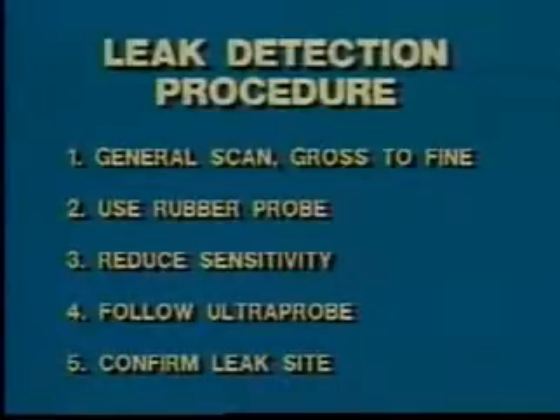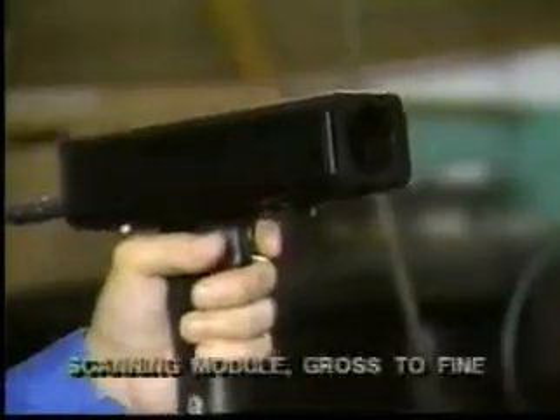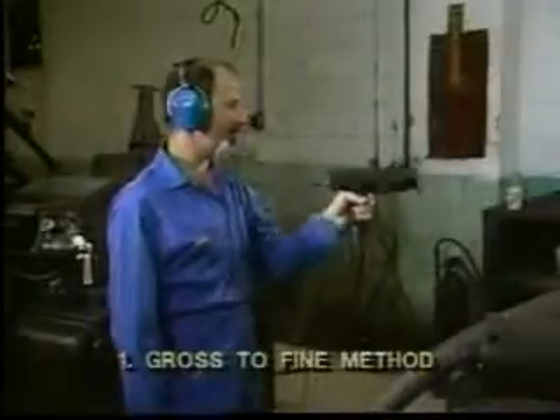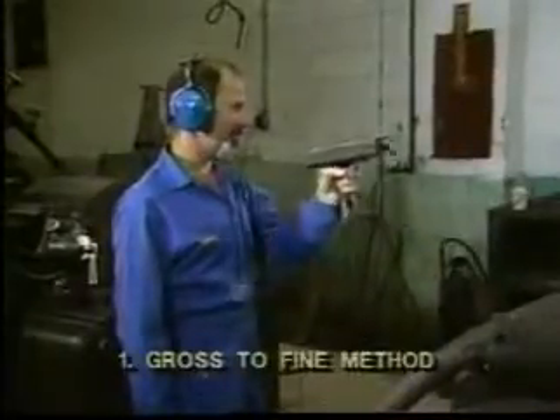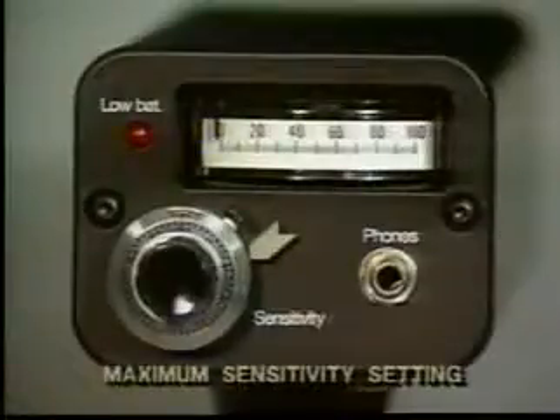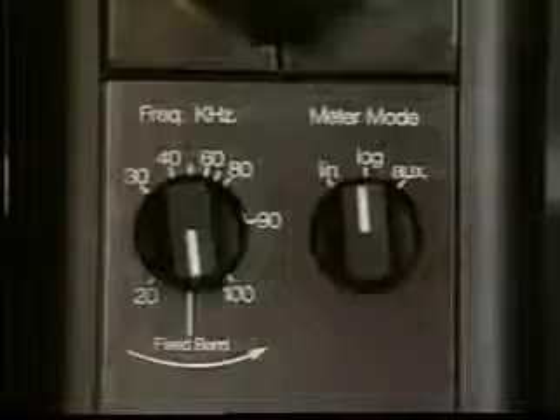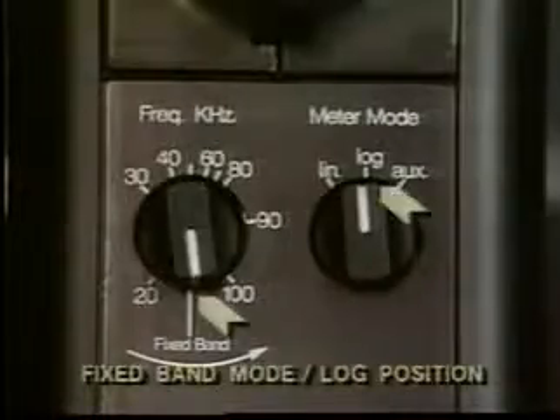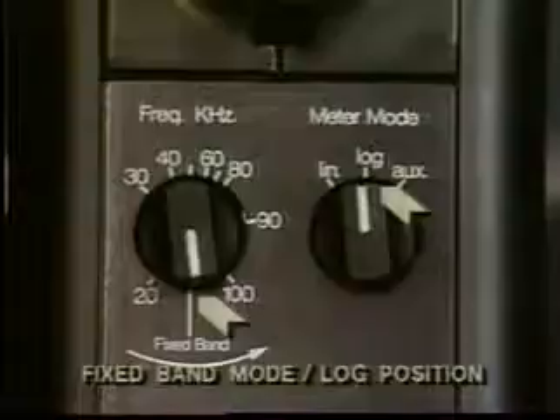Now we'll take a closer look at the leak detection procedure. First, using the Ultraprobe scanning module, we will follow the intensity of the signal to get closer to the leak site. This is the first step in what we call the gross to fine method. To pick up gross signals, scan with the sensitivity level set for most situations at maximum and use the fixed band mode. The meter mode should be in the log position. Scan the area, closing in on the leak site by listening for its characteristic rushing sound.